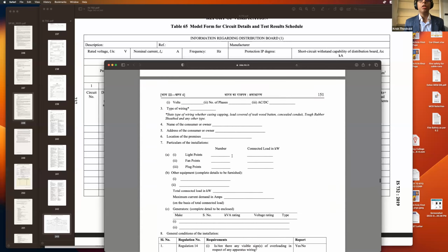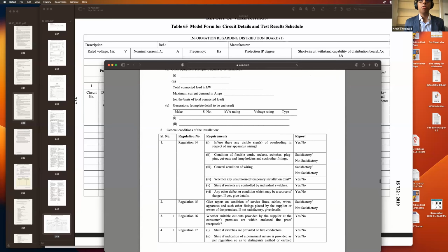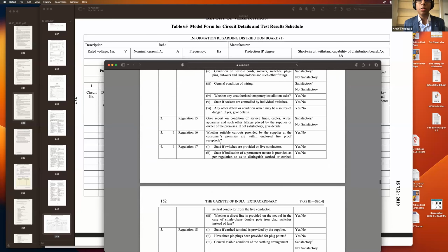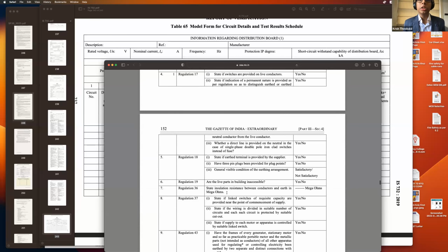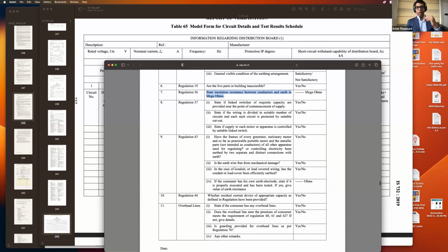If we look at the tests required, it just says, state insulation resistance between conductors and earth in mega ohms. That is a very weird question to ask, because are you asking me to plug my insulation resistance tester onto the entire installation and test between what conductors and earth? So it's very general.